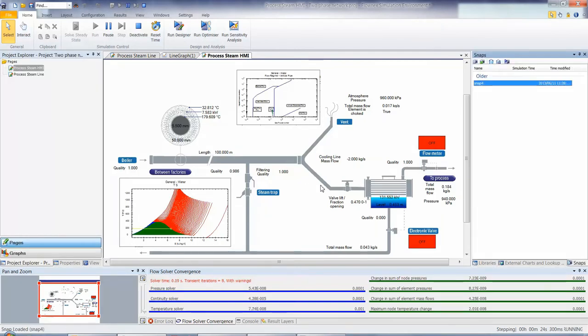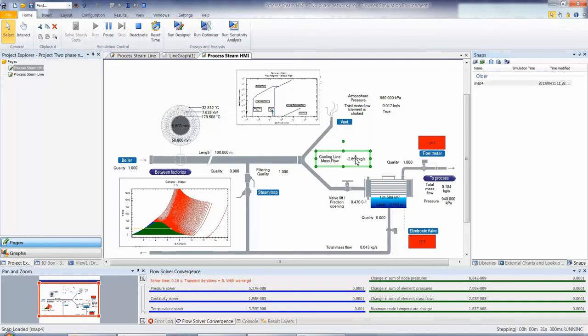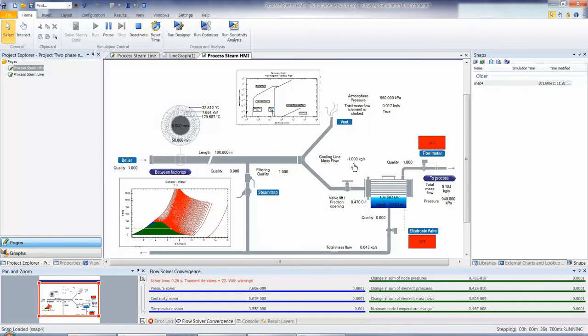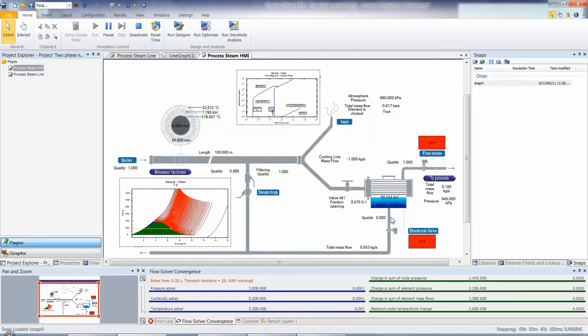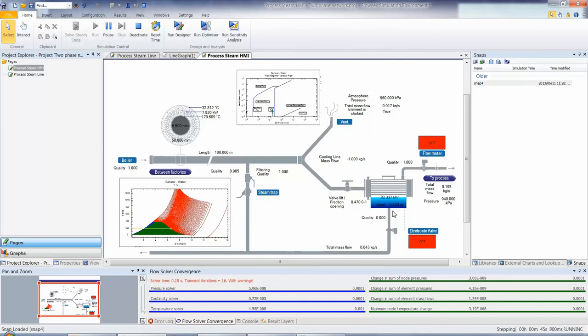So let's see what the effect of changing that cooling flow line back to 1 kg per second has on our system. Straight away we can see that decrease in flow, obviously decrease in heat transfer, and once again our level is going to be affected. Now what's important in this system is that total mass flow of the outlet. We want to maintain that mass flow to be at around 0.2 kg per second, and we also want to maintain the level within our condenser.